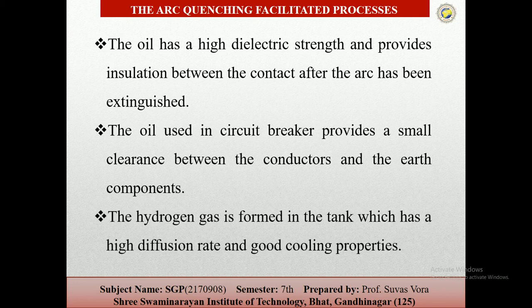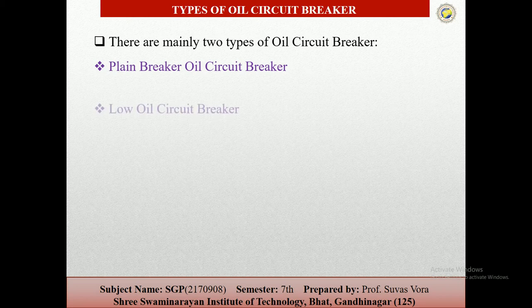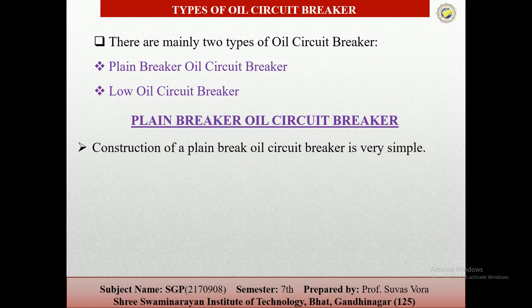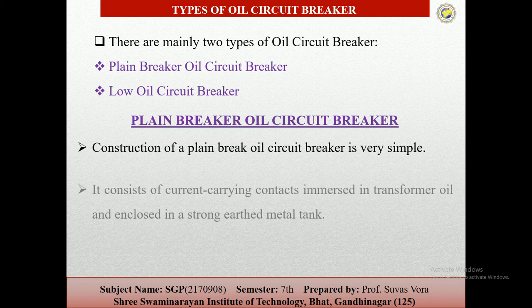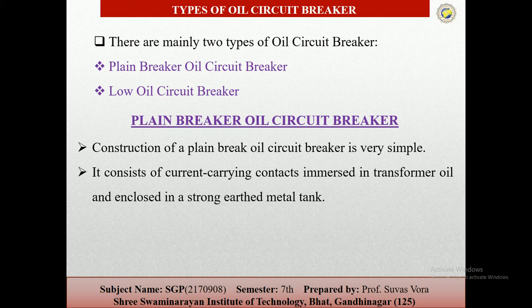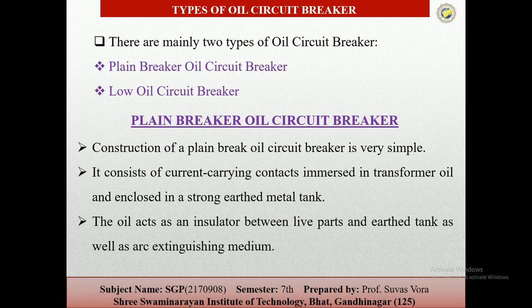Hydrogen gas is formed in the tank, which has a high diffusion rate and good cooling properties. This hydrogen gas or oil is used in the circuit breakers. Basically there are two types of oil circuit breakers: the first one is the plain oil circuit breaker and the second is the low oil circuit breaker. The construction of the plain circuit breaker is very simple, and it consists of current-carrying conductors immersed in transformer oil and enclosed in a strong earthed metal tank. The oil acts as an insulator between the live parts and the earthed metal tank, as well as the arc extinguishing medium.